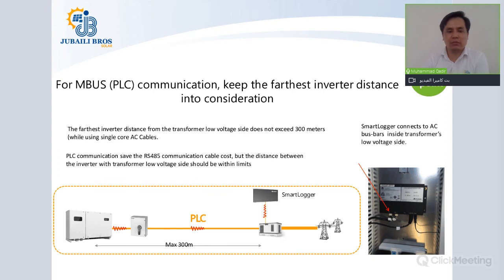PLC communication is used with our 36 kTL and above sizes of inverters, mostly for PV plants where your termination is happening on the MV cabinet. You have the option of going with the MBUS communication, which is also normally called PLC, power line communication. You do not need to lay RS485 cable in order to do communication of the solar inverters to the smart logger. So Huawei solar inverters can communicate via the smart logger. The smart logger is a device which logs the data and transmits it to the FusionSolar Cloud, from where you can retrieve the data by making a plant on our platform, FusionSolar.